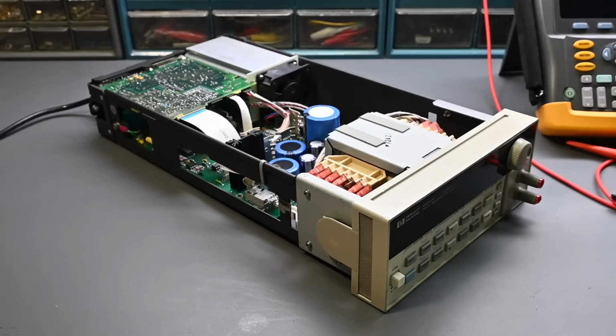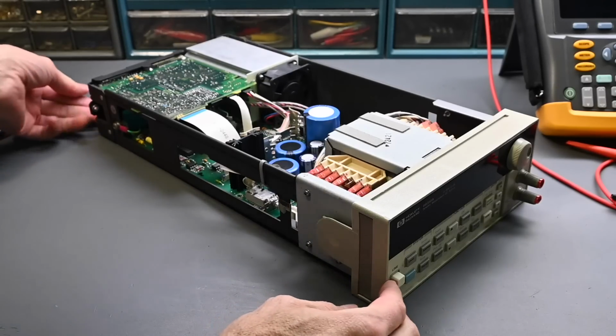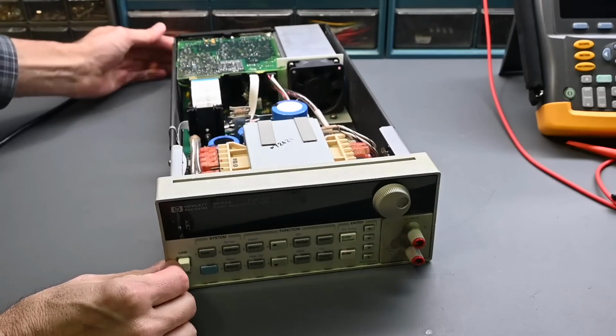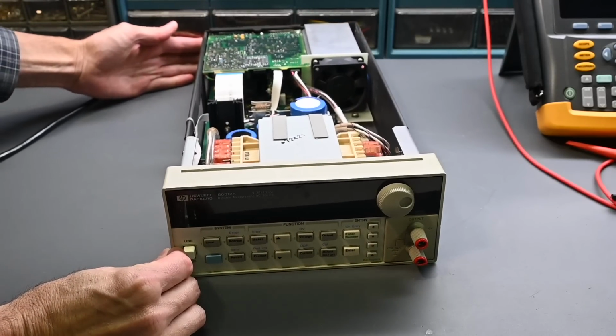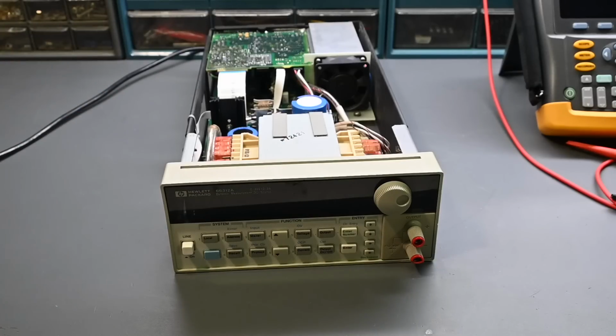So depending on how the troubleshooting goes and how the power supply functions or what happens, if we get to that point of taking these measurements, I just want this to be earth grounded, because it's intended to have the chassis at earth ground potential, as well as the neutral should be at earth ground potential and not just floating. All right, so let's get this powered up here and see what happens. So turn that there, I think you can see that. All right, here we go.